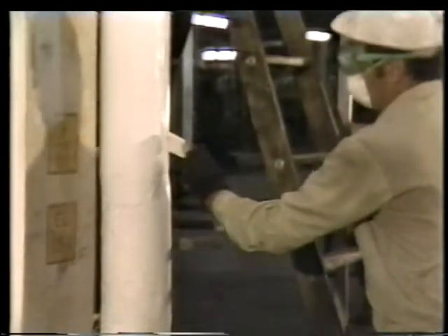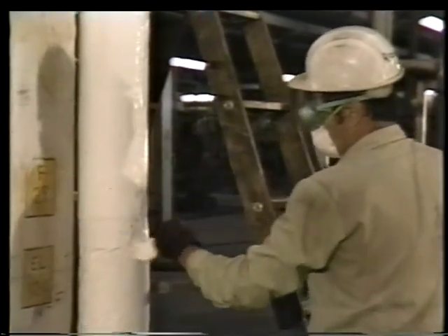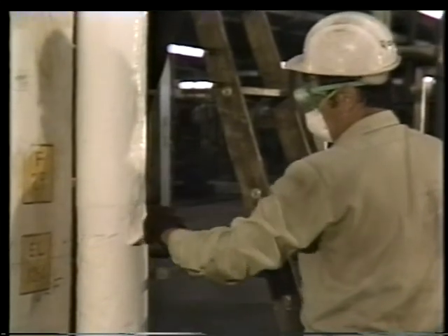The seams are covered with cement to help seal out moisture that would tend to condense on the pipe in warmer weather. A good thick coating seals in the seam and plugs up the holes made by the staples. Working with fiberglass isn't difficult. It's light, easy to handle, and any special trimming can be done with a sharp knife. The example we've just seen demonstrated was the installation of pre-made fiberglass insulation for piping systems.